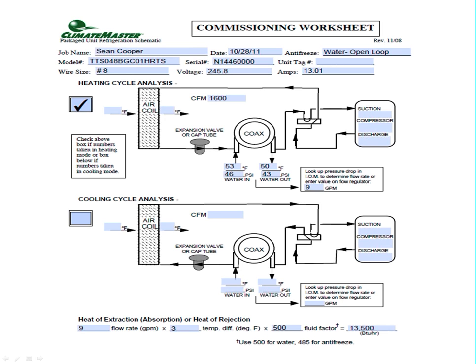So let's talk about what this is showing us. You have a couple of choices here, and let me give you my strong recommendations. Because this is open loop, we have sufficient fluid flow, we have good airflow, and we're just not transferring the temperature through the heat pump. It's not necessarily a refrigeration issue, and in fact on open loop it probably isn't.